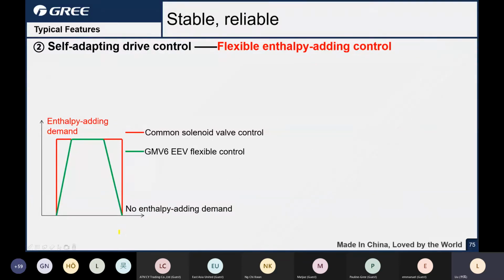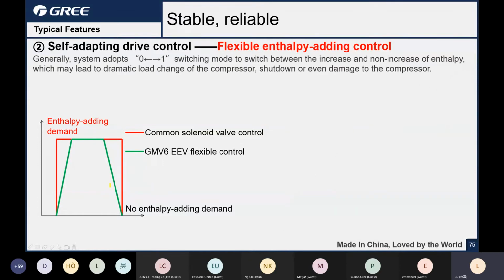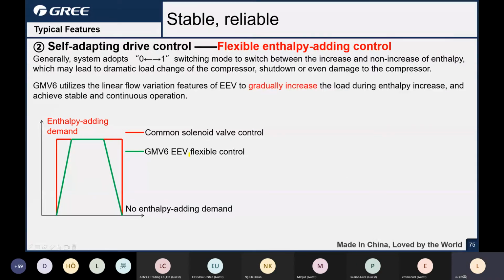And next one is about the enthalpy adding control. That's what I introduced in the previous slides. It's about the EVI, expansion valve. For some brands, they use the solenoid valve for enthalpy adding. If there is a need to use the enthalpy, the solenoid valve opens and injects the vapor to the compressor. However, GMV6 uses the expansion valve. That means the control is more flexible and precise. It can gradually increase the enthalpy amount by the demand.